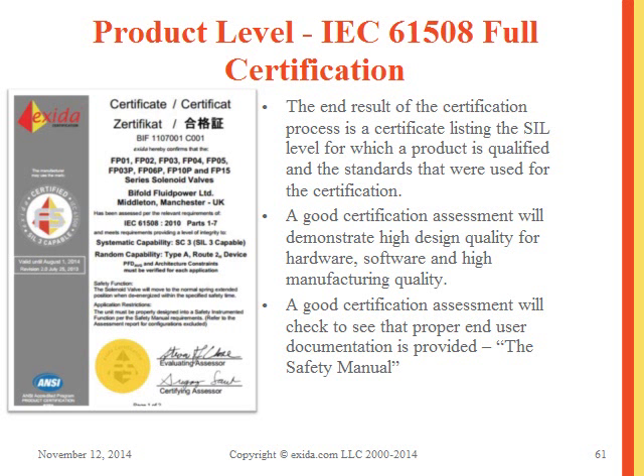The end result of a full certification process is a product certificate and an assessment report. The certificate lists the SIL level for which the product was qualified. Products can receive full certifications with restrictions — look for those in the safety manual. On the back of the certificate, Exida lists the dangerous and safe failure rates. Look for both — you don't want something with acceptable dangerous failure rates but safe failures through the roof, as that will result in too many spurious trips, plant shutdowns, and wasted time and money.